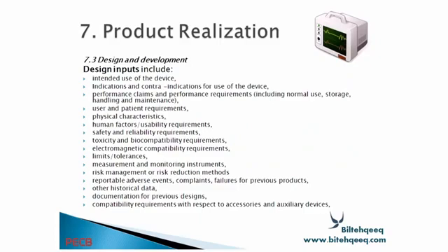And design input includes intended use of the device, indications and contraindications for use of the device, performance claims and performance requirements including normal use, storage, handling and maintenance, user and patient requirements, physical characteristics, human factors, usability requirements, safety and reliability requirements, toxicity and biocompatibility requirements, electromagnetic compatibility requirements, limits, tolerances, measurements and monitoring instruments, risk management or risk reduction methods, reportable adverse events, complaints, failures of previous products, other historical data, documentation for previous designs, compatibility requirements with respect to accessories and auxiliary devices.